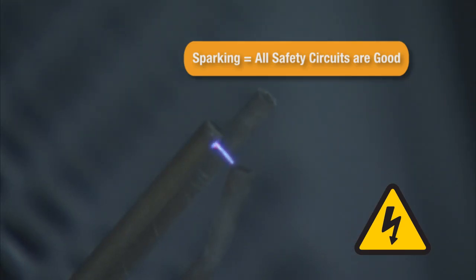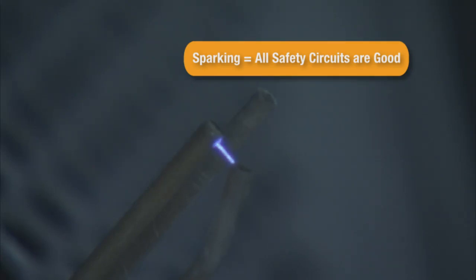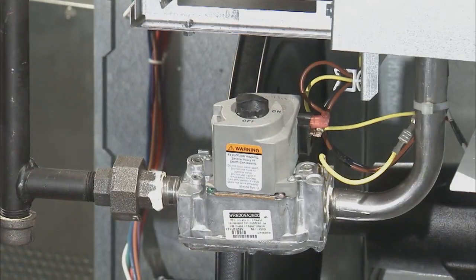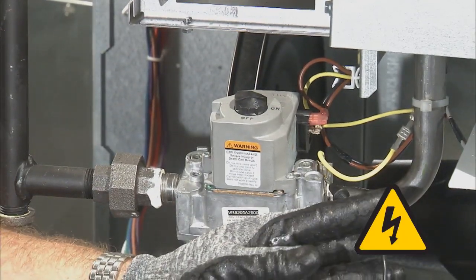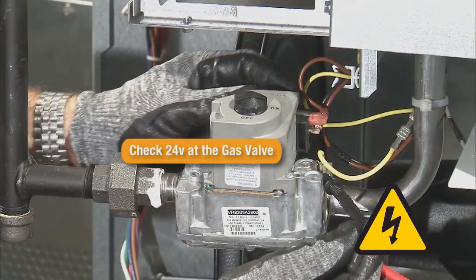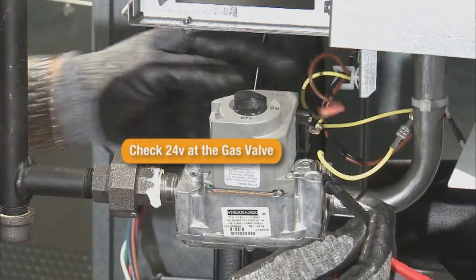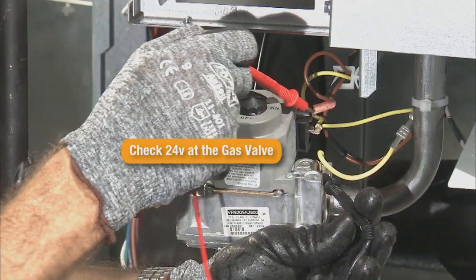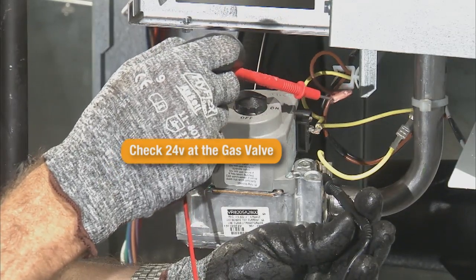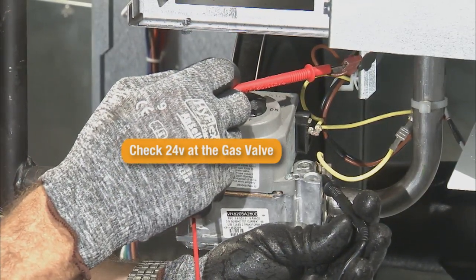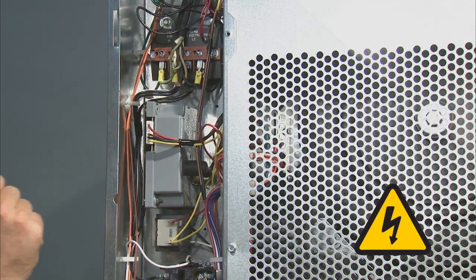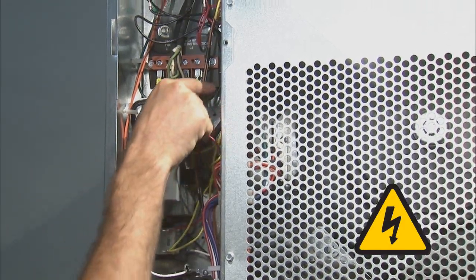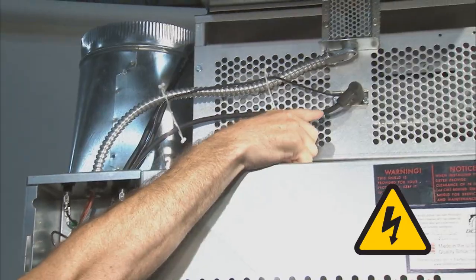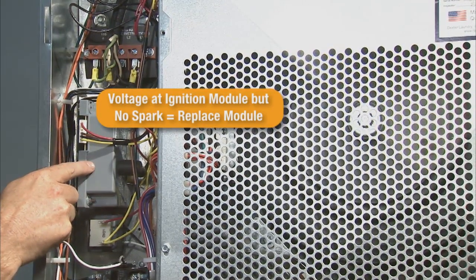When troubleshooting, the sparking noise is an indication that all safety circuits have been achieved and that the unit is attempting to heat. To test the gas valve, place the black lead of the meter on the yellow wire and the red lead on the brown wire while the ignition module is sparking the igniter. At that time, 24 volts AC should be present at the brown wire of the gas valve. At the same time, the ignition module should be sending the high voltage for the spark. Look and listen for the spark. If there is no indication of sparking, replace the ignition module.